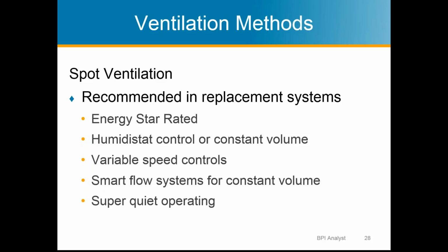Smart flow systems is that constant volume, where in any ducted system, there's going to be restriction just due to the ducts. So a smart flow system will adjust the fan speed to make up for the pressure in your duct as you take that air out of the house, because sometimes it might be 4 feet long, sometimes it might be 8 feet long. So a good fan is going to adjust for that.